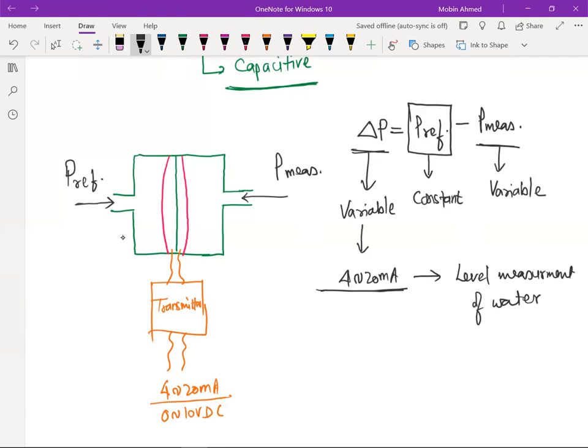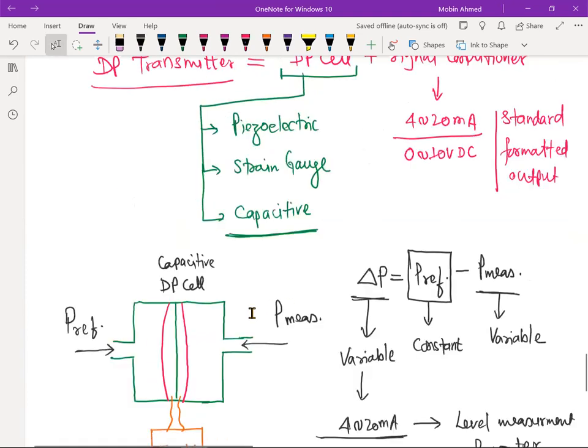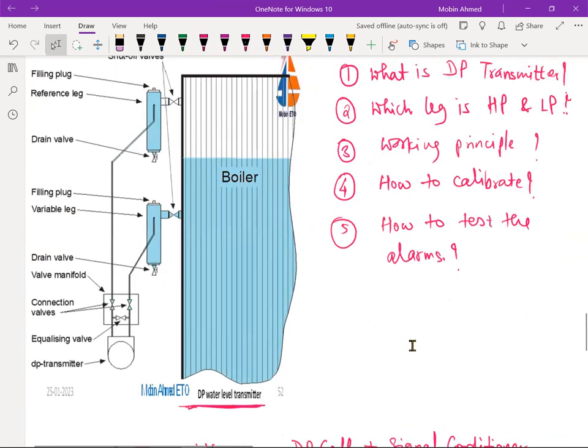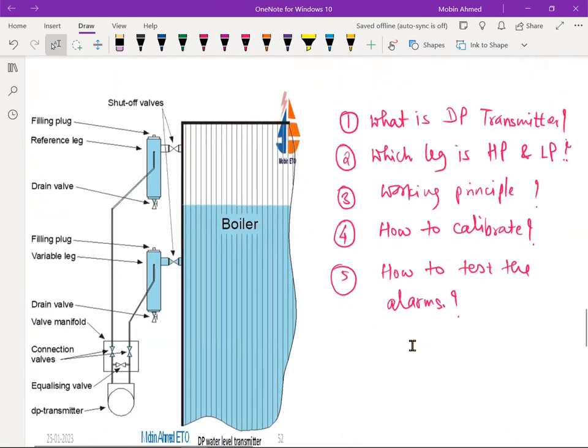So this is a DP cell, capacitive type, what I have made here. This capacitive DP cell, or any DP cell, is going to have two pressure inputs, and accordingly it is going to give the output 4 to 20 milliampere. This is how it works. Now coming back to this one.